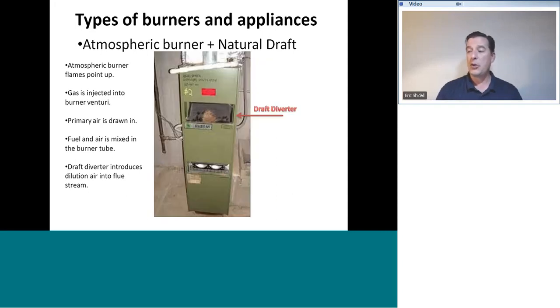Here's a draft diverter on an old Rheem furnace. This is a furnace from the early to mid-1980s, probably a standing pilot. Two burners, here are their openings down here. Primary air involved in this direction. Secondary air joining the flame already in progress. Dilution air coming up at the top of the furnace where the draft diverter is and going up the vent upwards.